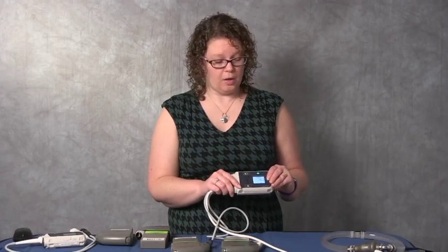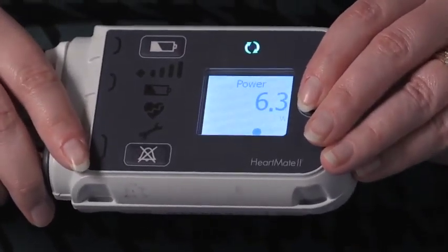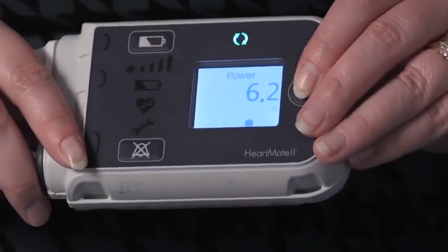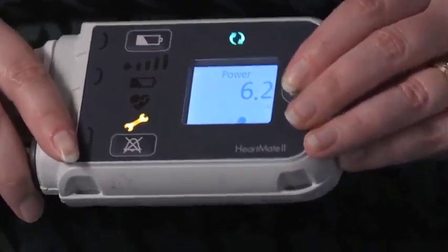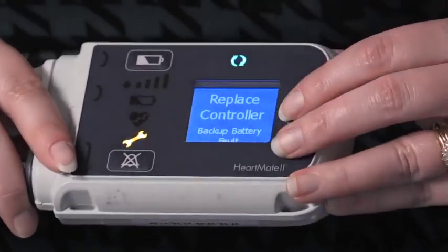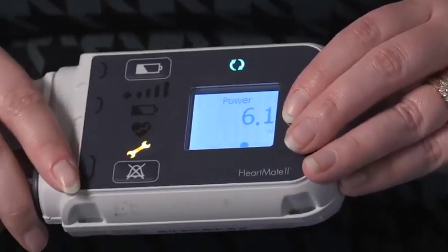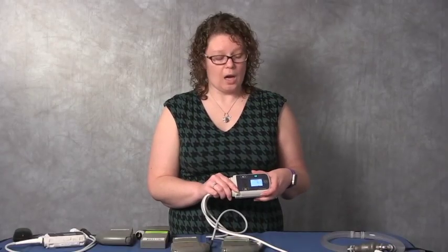The fourth number that comes up is the pump power, and this is arguably the most important number that the VAD will give you. What we're measuring is power consumption of the pump. How much power is the pump using to achieve that set speed, in this case of 9600. We were at 6.1 watts. And the reason that I worry about that is because if the speed isn't changing, but the pump needs more power to get there, then I'm concerned about some sort of obstruction. And that obstruction could be a blood clot that's forming on the rotor of the pump, or it could be high blood pressure that's acting like an obstruction.